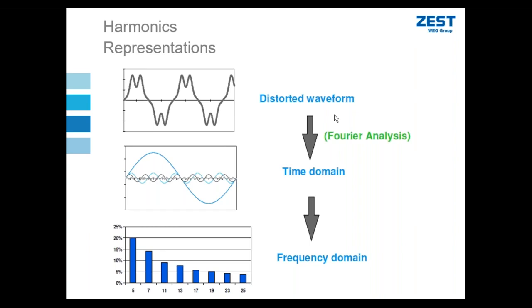Just to show you, there's a few ways we can represent a distorted waveform and harmonics. The most rudimentary way is to display graphically, on the time domain or frequency domain, the actual distorted waveform itself. We can break that distorted waveform up into its fundamental plus a series of harmonic frequencies which add together to create that distorted waveform. This becomes a lot easier for analysis and comparison.